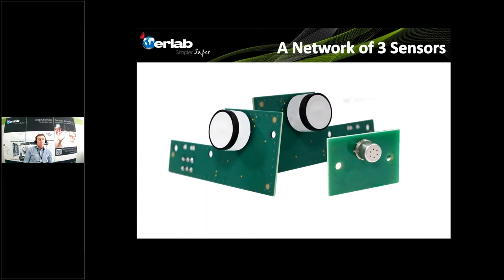In the GFH, we use a network of three different sensors. The first is a semiconductor sensor used to monitor a large variety of VOCs. It is very sensitive, and for most applications it is sufficient because it reacts each time there is a VOC at very low concentrations. However, it is sensitive to acids but can be damaged by them, which is why we combine it with a sensor for acids and an optional sensor for formaldehyde.